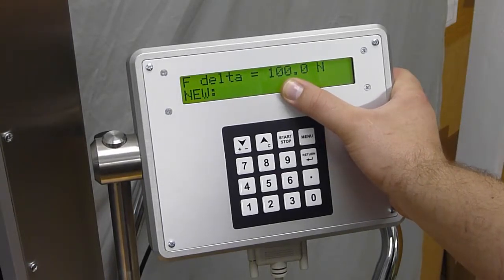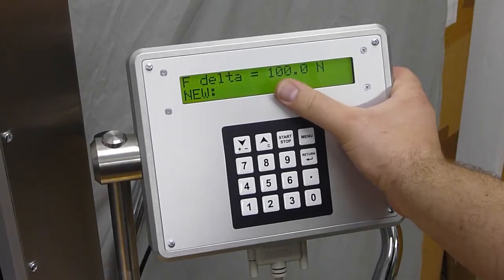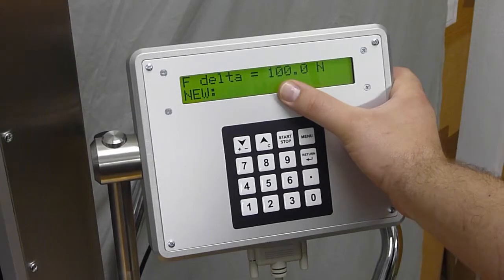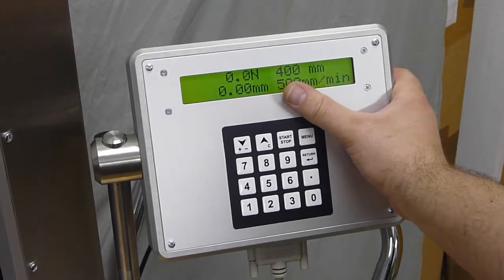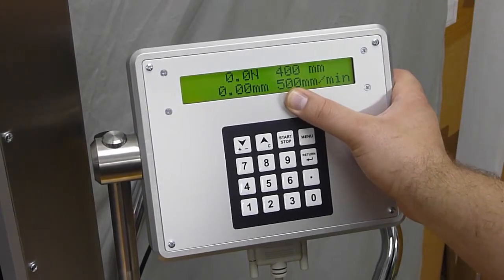if force falls down over 100N, break detection is active. The machine makes 50 measurements per second, so each 20ms is one measurement point.